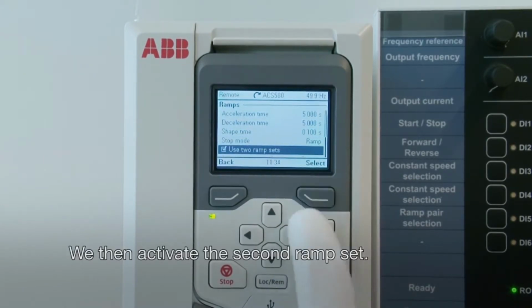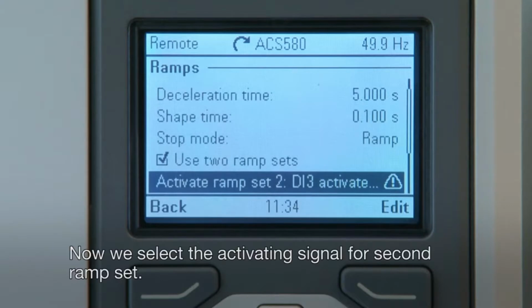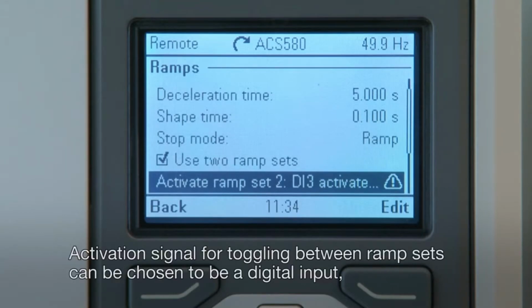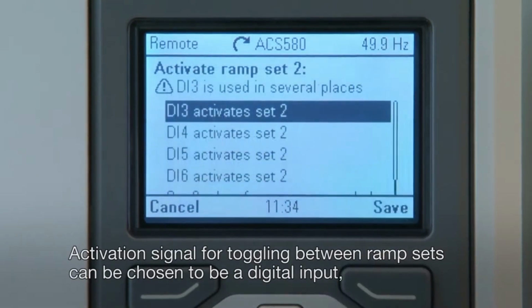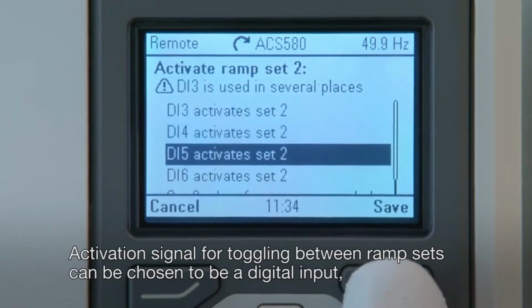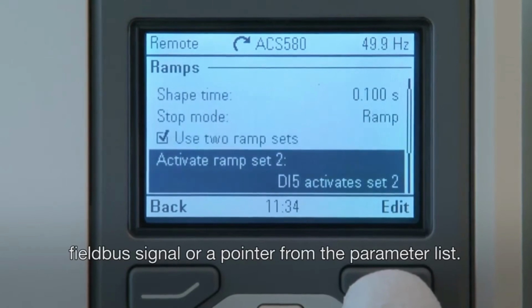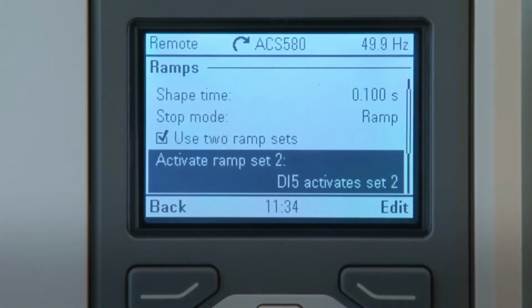We then activate the second ramp set. Now we select the activating signal for the second ramp set. The activation signal for toggling between ramp sets can be chosen to be a digital input, fieldbus signal, or a pointer from the parameter list.